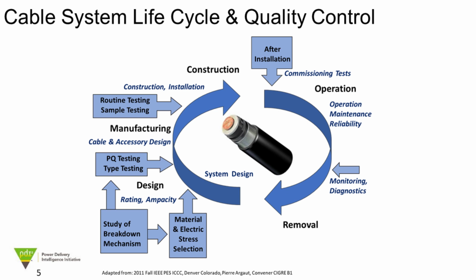The jacket is tested, whether it's high voltage or medium voltage. High voltage is tested with what we call the jacket integrity test because it has a conductive layer on the outside. Medium voltage is tested using the spark tester. We make sure that the jacket is intact. The jacket, as everybody knows, plays a major role in the protection of the cable and ensuring its long life in service.